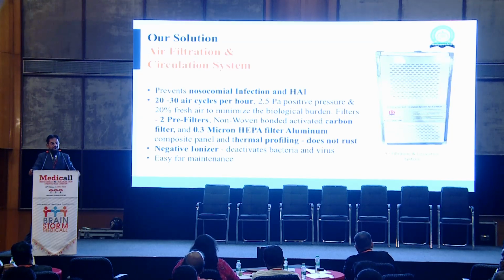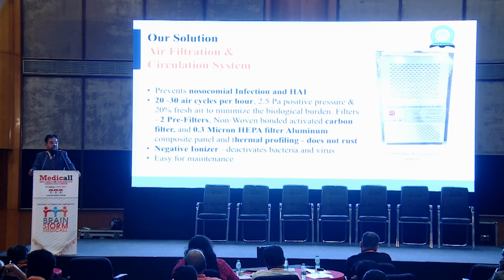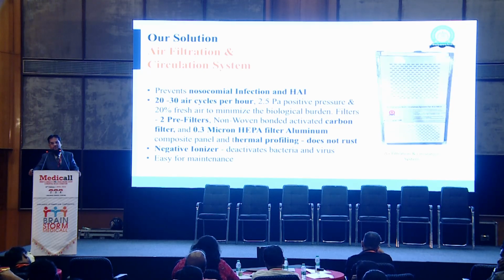I had installed these systems in one of the CVTS ICUs, where they do cardiac, heart transplant, liver transplant, all these critical patients where recovery is challenged and survival is also challenged. In that area, when I gave the systems, earlier they used to require 5 to 6 weeks to discharge patients. Now, after installing this, they get discharged within 2 to 3 weeks. All post-op complications will be taken care of. This system will give 20 air changes in the ICU. Then activated carbon filter and HEPA filters have been given. So whatever air is coming through the HEPA, the particle counts will be minimized, and you are getting the air changes also. So this is the beauty of the systems.